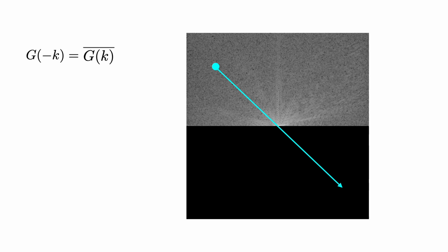So if our image was real, then we could only sample half the Fourier space and still reconstruct a high-quality image. Unfortunately, our image is not real because of inhomogeneities in the main magnetic field or in the excitation pulse or errors in the gradients. So what do we do? We collect more than half, slightly more than half, about 5/8 of the data. Then we use the center region to estimate the phase. Assuming that's the phase, the rest of the image is real, and we reconstruct accordingly.